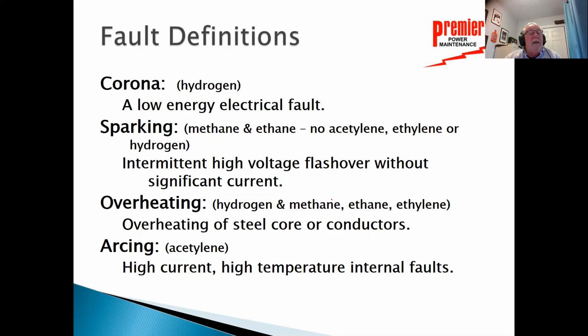That would be a case where I might have an intermittent high voltage flashover, but there's not a lot of current involved with that. I could have overheating where I've just overloaded it, or maybe I've got a hot spot. Hydrogen, methane, ethane, and ethylene could all be indicators of that. Arcing, high current, high temperature internal faults, acetylene would be an indication of that.